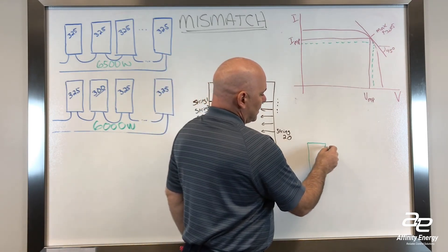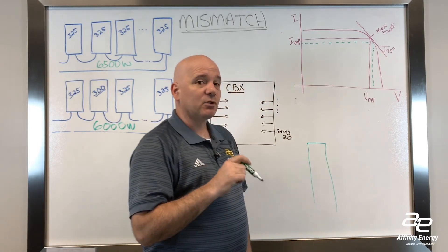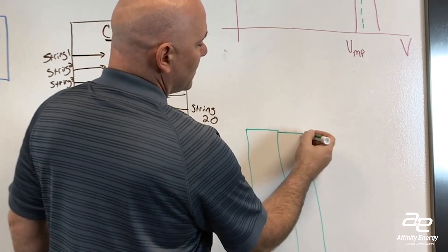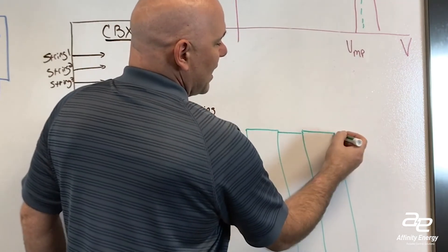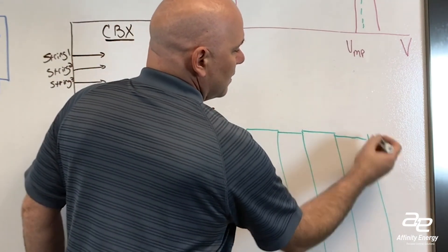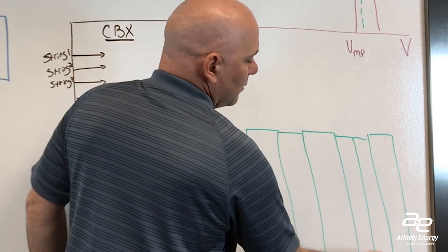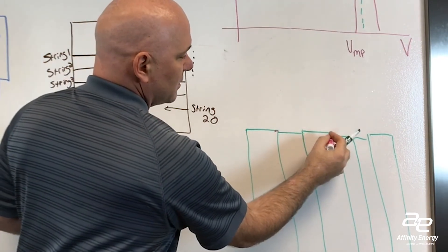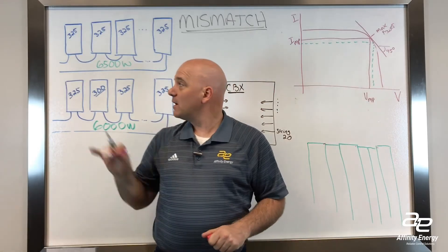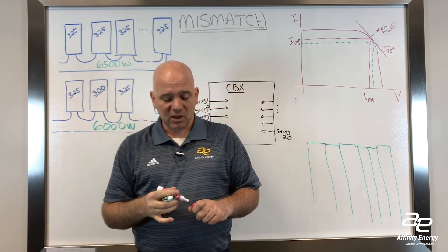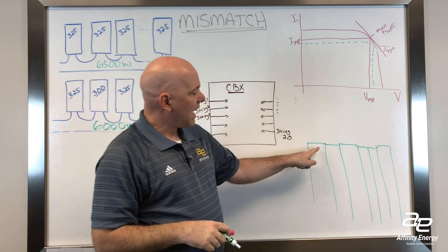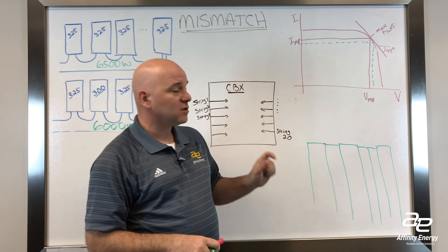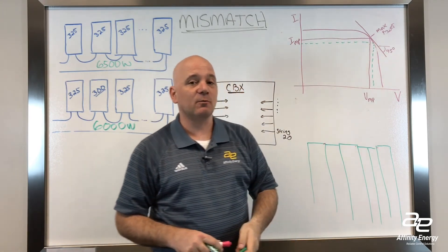As a final thought, when you normalize the data, what you might see is the average current per string from each combiner box in your plant. If you have a very small difference from one to the next, over time this difference might not be super impactful. But these little tiny differences will add up, and something as small as one missized module or a module with a crack will have an effect on the total output from the combiner box — because that one small change is trying to move everything in that combiner box around on its max power point.